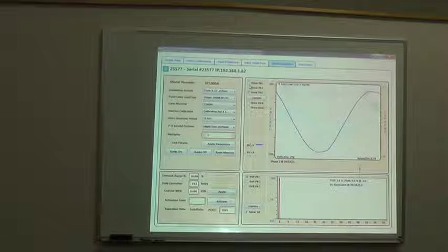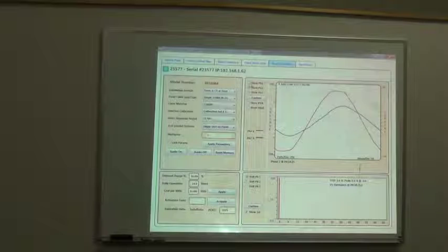Yeah, we went over that some yesterday. But without that scope, you're not going to really know that. There's no other way, so that's the benefit of it. But honestly, the most important thing that you can use the scope for is to diagnose wiring problems, installation wiring problems. That's the only way to do it. For the SP1000, like the CT rotation, position.